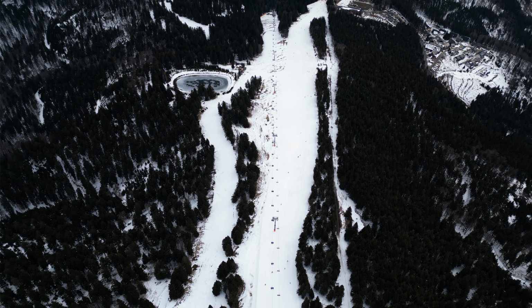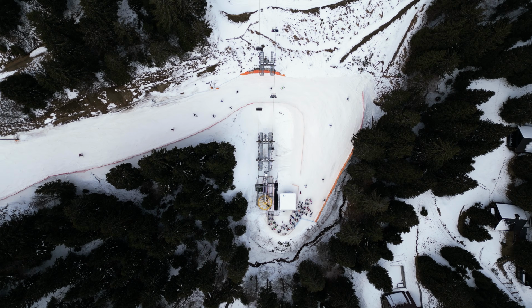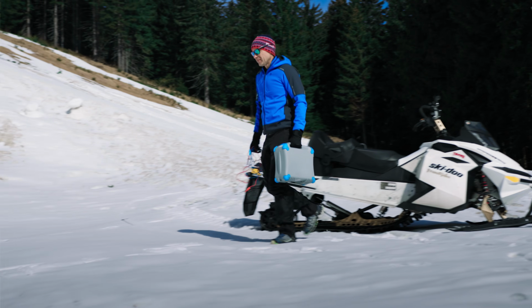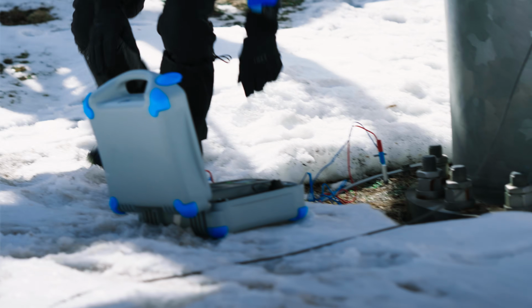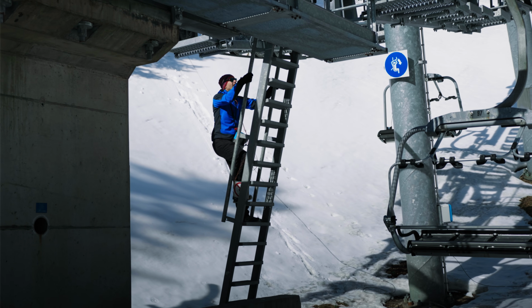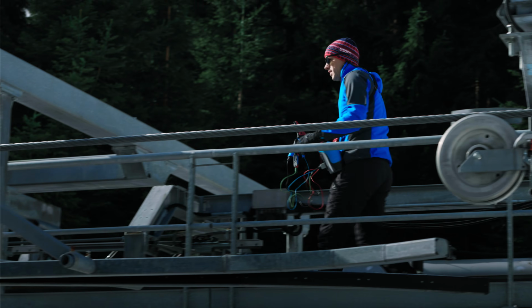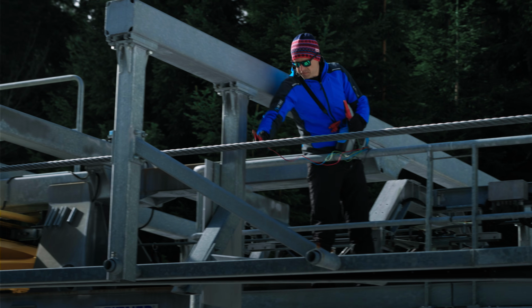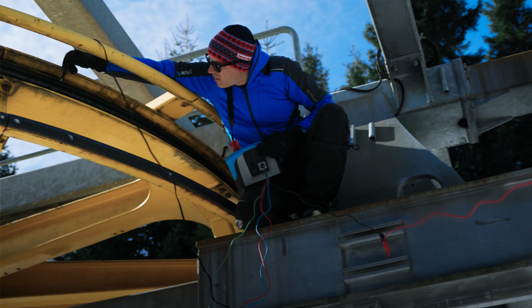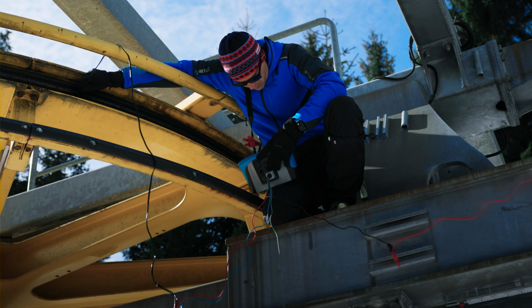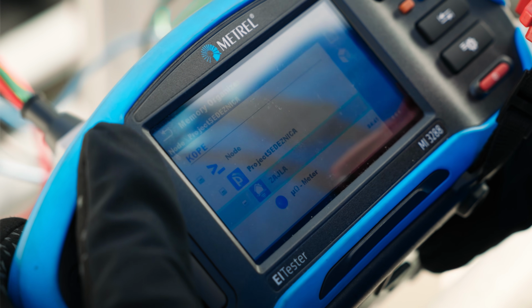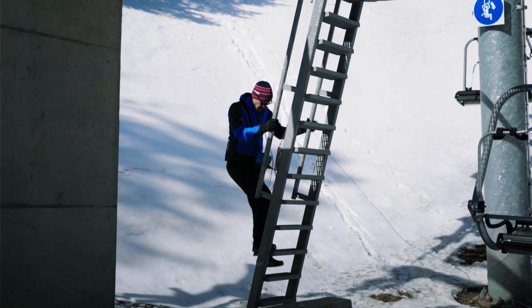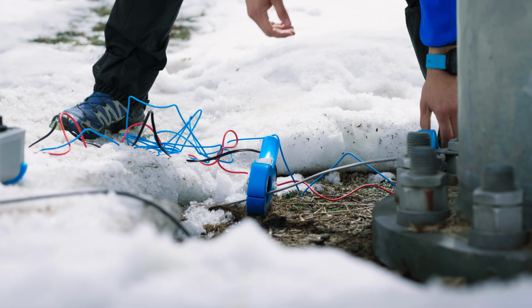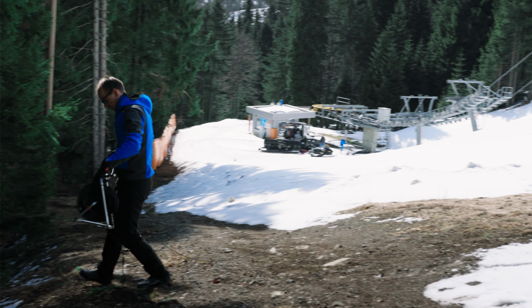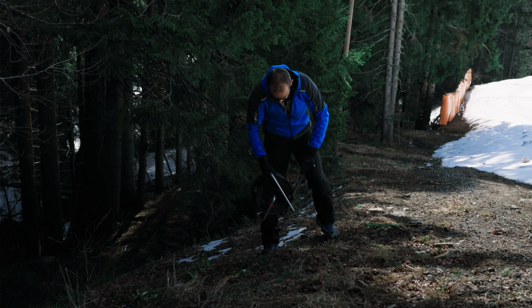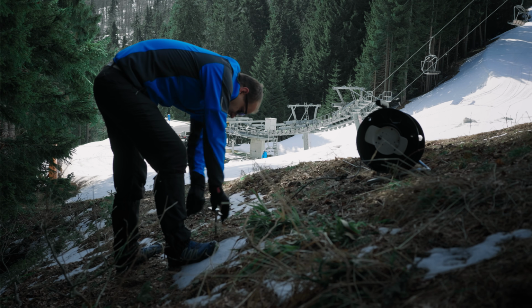Why wait for summer when all essential measurements can be performed in winter? Our robust solutions make measurements easy and reliable, even in challenging winter conditions. We start by identifying the grounding system at the lower station. This involves checking continuity with a 2-amp current, using the accurate 4-wire method between the drive unit and the carrying cable, and verifying connections to earth. After that, we apply the 2-clamp method to determine whether the system is unified or isolated. This step answers the question: are the towers locally grounded or linked to the station?